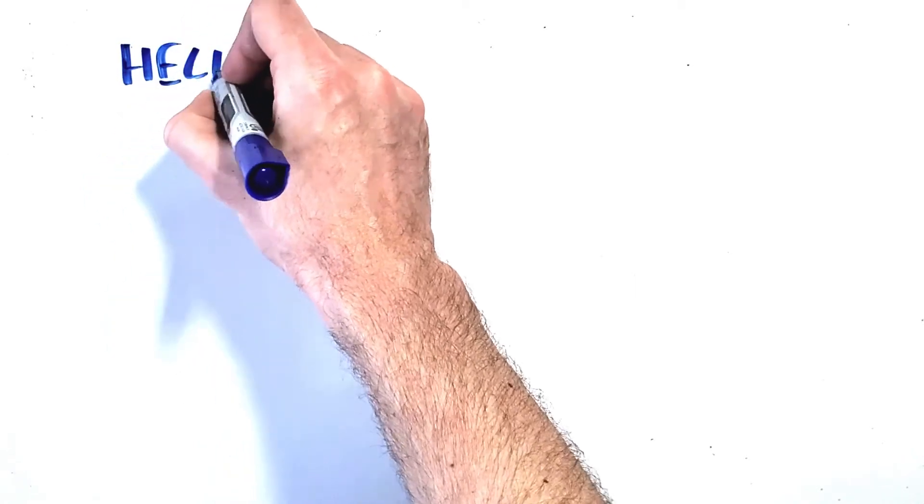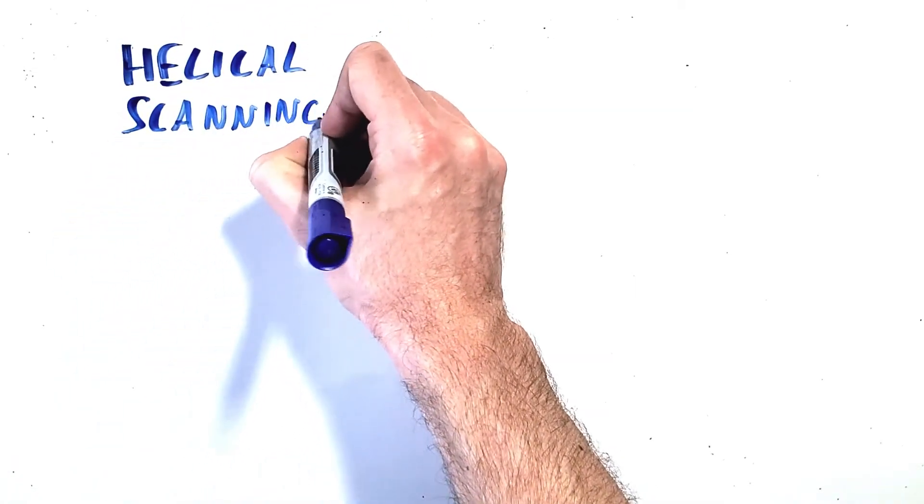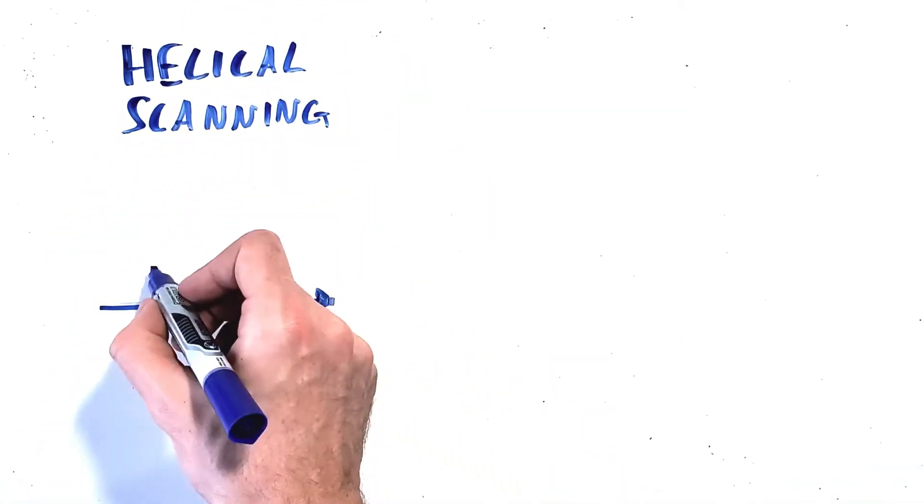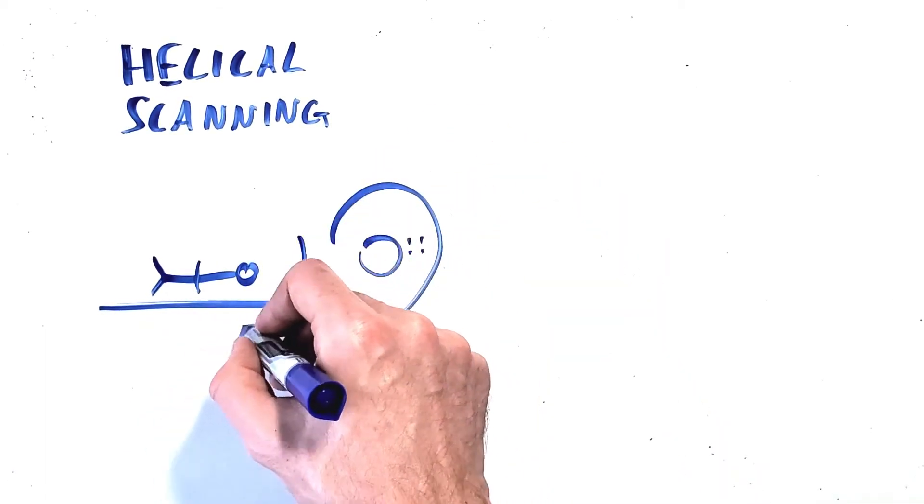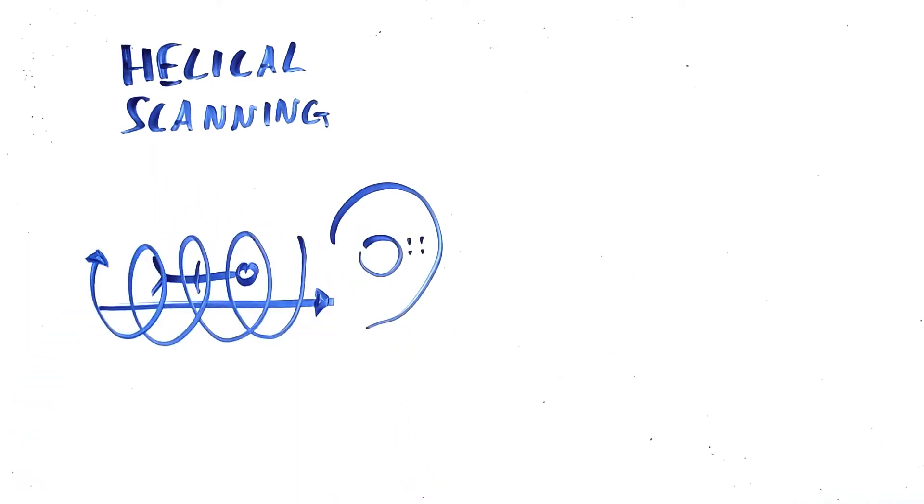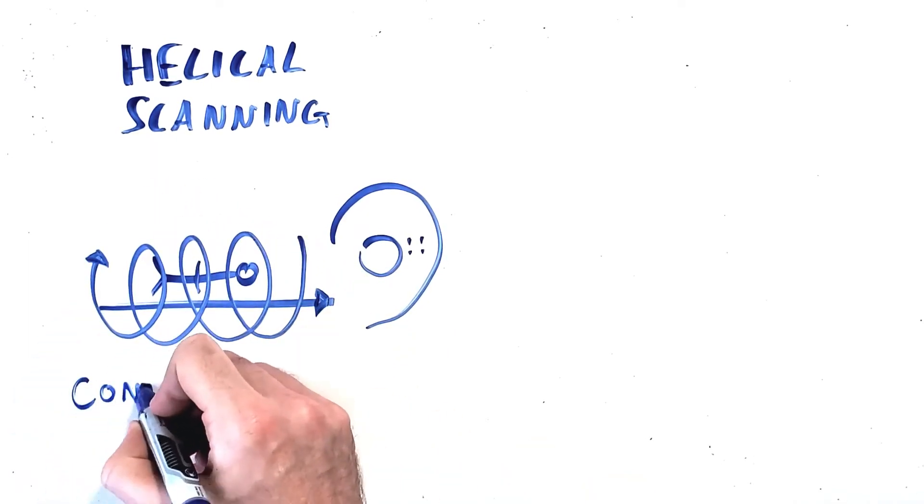This is significant because it allowed for the continuous acquisition of data in what's called helical scanning where the scanner acquires data in a spiral pattern wrapping around the patient acquiring continuously while the patient moves through the scanner along the z-axis.